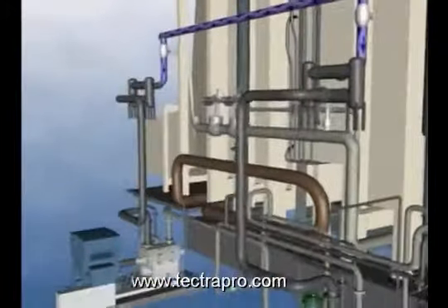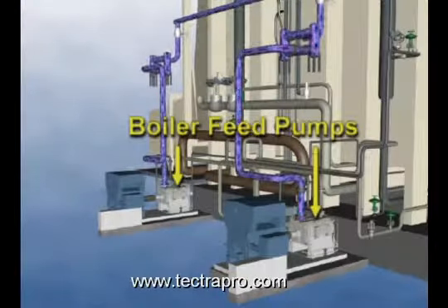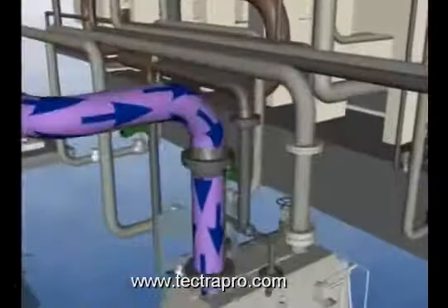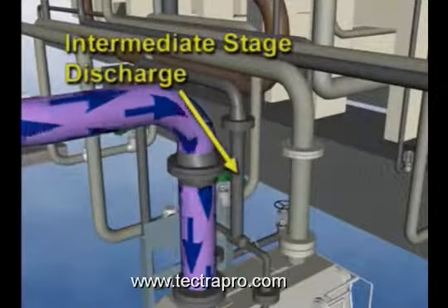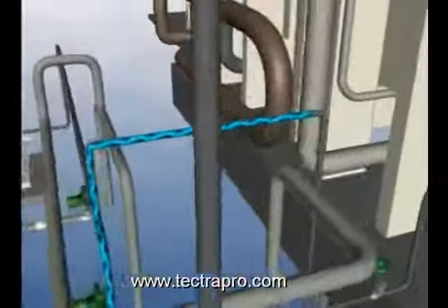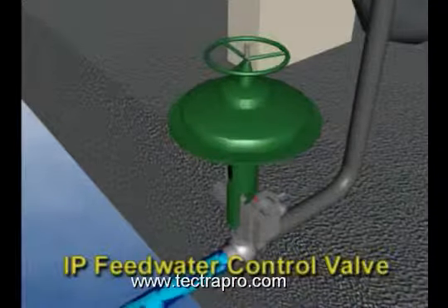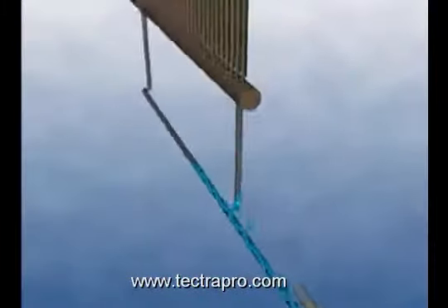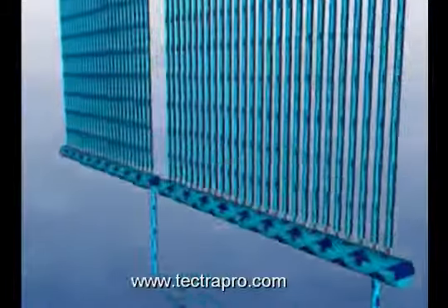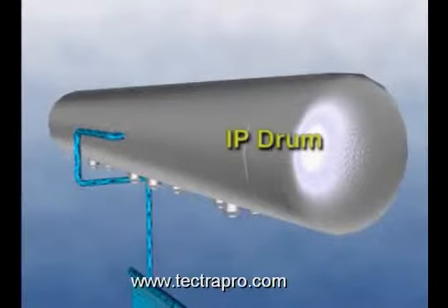Water from the LP drum is supplied to one of 2 boiler feed pumps. The water is pumped from an intermediate stage of the boiler feed pump through a flow control valve and one IP economizer rack to the IP drum.